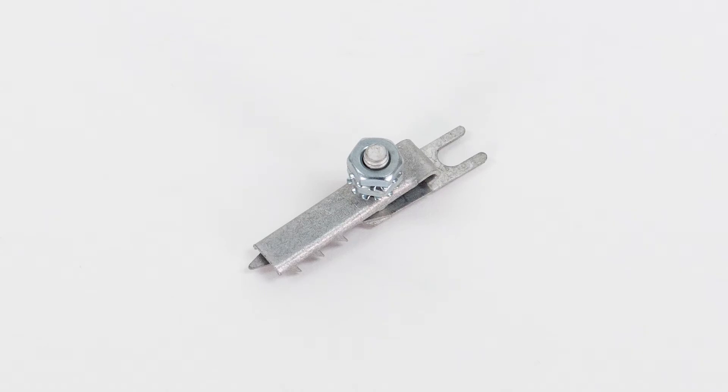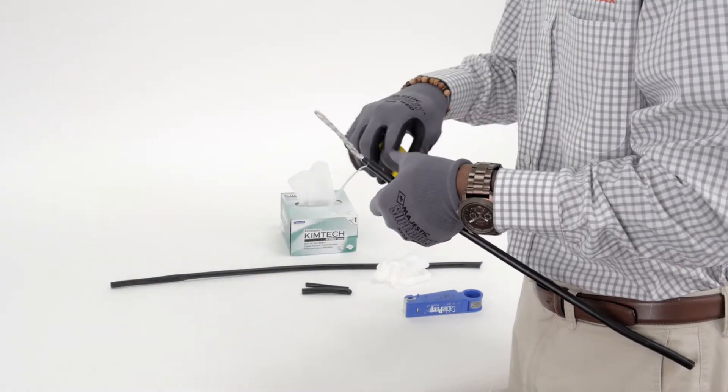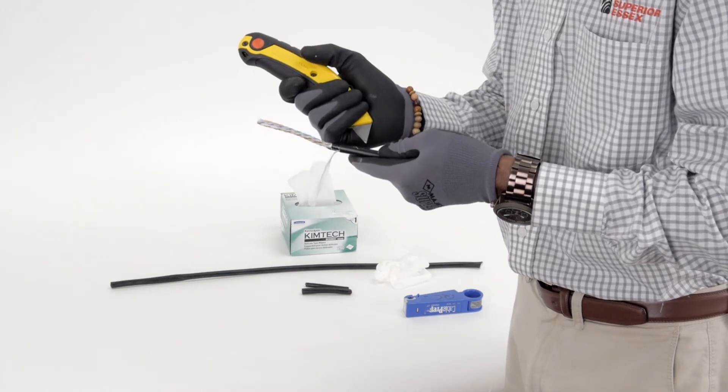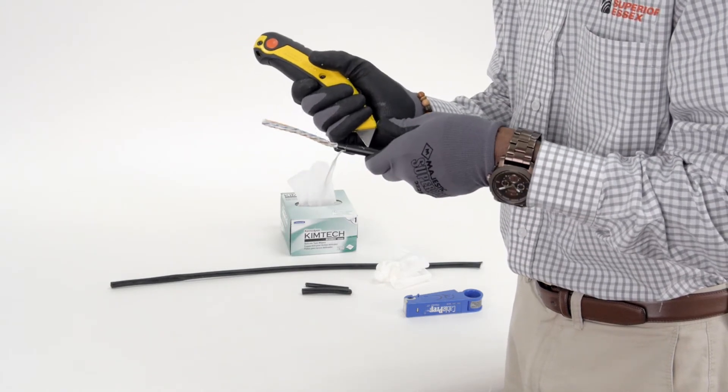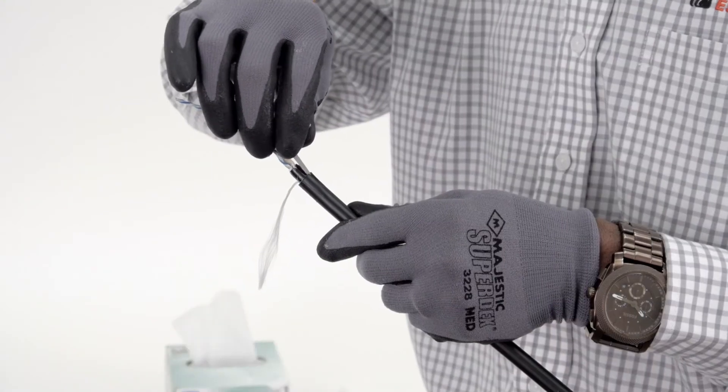The preferred method of bonding is to use a bullet bond that slides over the inner jacket underneath the shield. To accommodate the bullet bond, make a longitudinal cut of about 1 inch depending on the bond design in the outer jacket and shield to allow the outer jacket and shield to flare over the bullet bond.